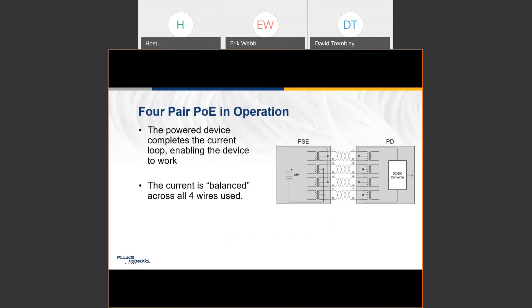One of the problems you'll see is that the cabling has to have low resistance — because if there's too much resistance, the cable will heat up, the resistance goes up further, and the power starts to not get through. The other issue, perhaps less apparent, is that the resistance needs to be balanced across the pairs. Otherwise one pair will try to carry more power than another. Even within a pair, if one wire has significantly more resistance than the other, you'll end up with transformers getting saturated in the powered device. While the powering may still work, the data won't be able to get through.